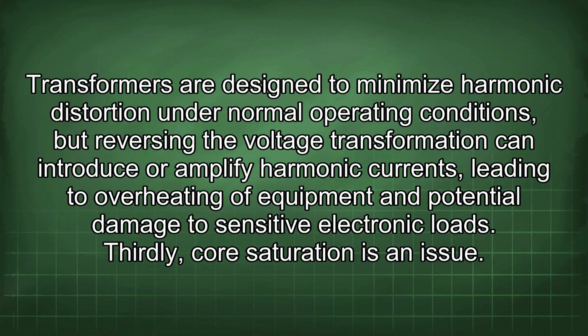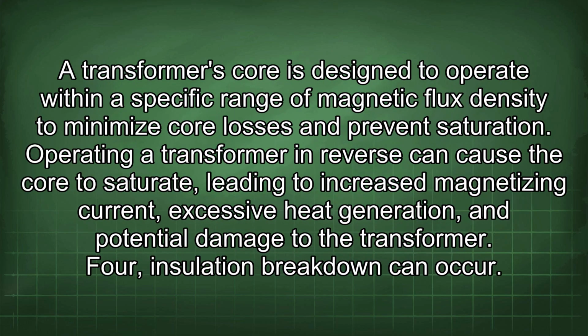Thirdly, core saturation is an issue. A transformer's core is designed to operate within a specific range of magnetic flux density to minimize core losses and prevent saturation. Operating a transformer in reverse can cause the core to saturate, leading to increased magnetizing current, excessive heat generation, and potential damage to the transformer.